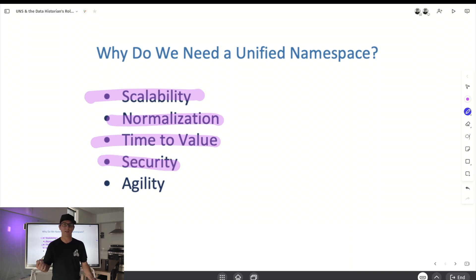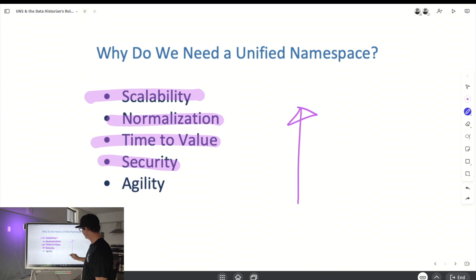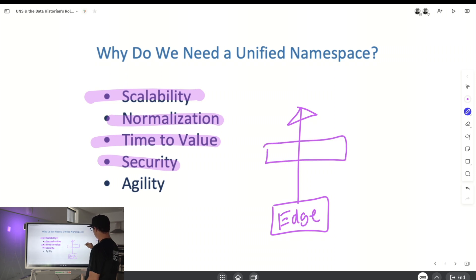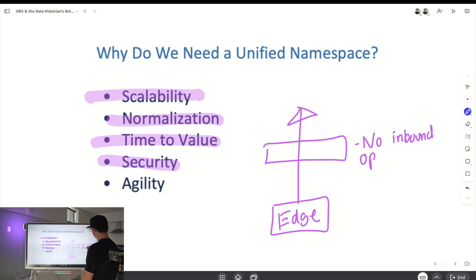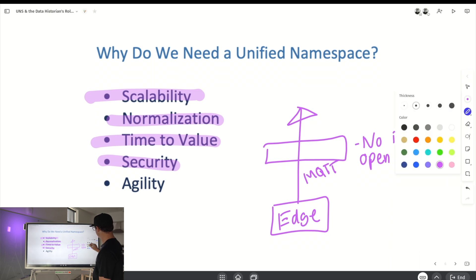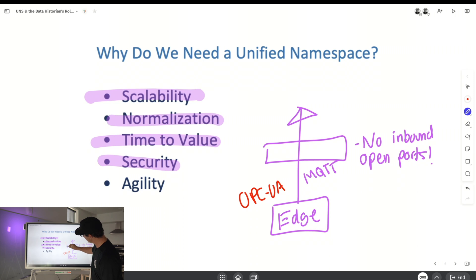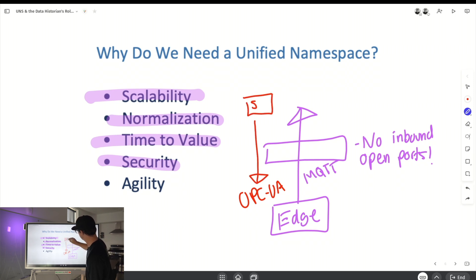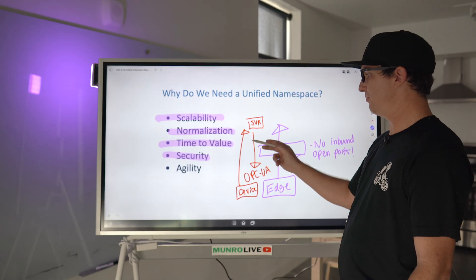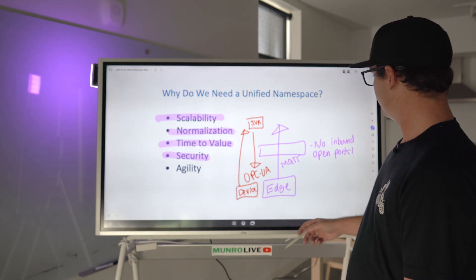Security. Number one thing we love about this type of architecture: outbound only. Devices from the Edge can publish their data out through a firewall with no inbound open ports. This is going to make your IT team really happy, especially if you're using MQTT. With OPC-UA, you'd have to open inbound ports for the server to poll the device — with MQTT, no inbound open ports. Outbound only.